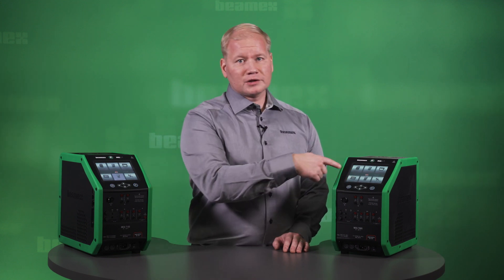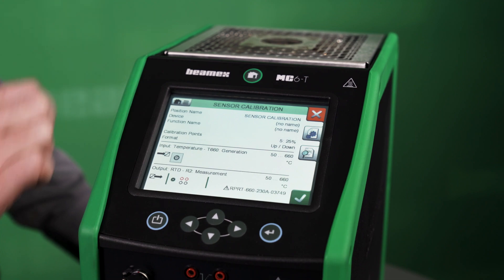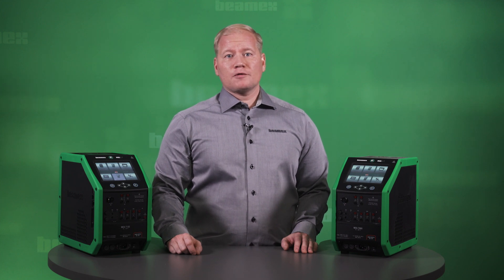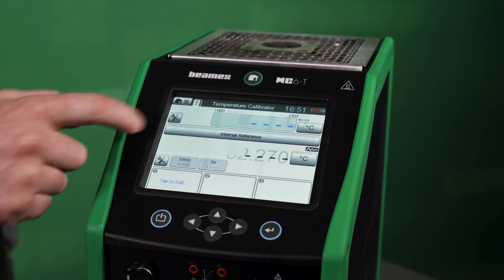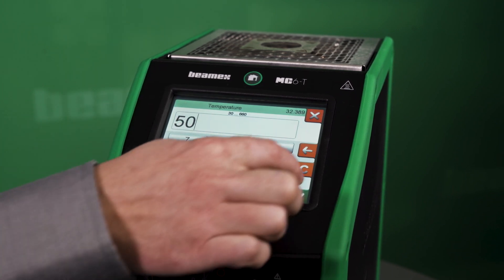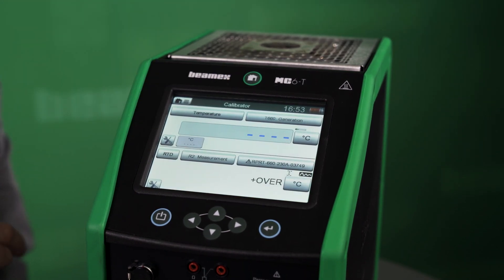The MC6 has a large 5.7-inch multilingual color touchscreen that can be used with bare fingers, gloved hands, or a stylus. The user interface provides a QWERTY and numerical keypad for fast and easy usability. Alternatively, there are also membrane keys that you can use to control the device. The user interface is divided into different applications for easier use. The first mode is the temperature calibrator, which is a quick and easy way to use the temperature block to control temperature and measure additional channels. The calibrator mode has two windows for instrument input and output — classic Beamex style.